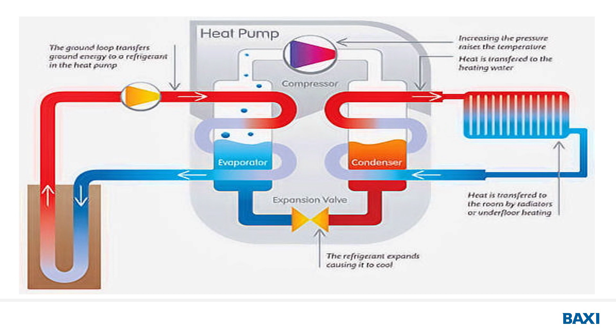The job of the CHP was to be brought into use when the building required extra heat that the ground source heat pump couldn't provide. The CHP would then be diverted to supply the heating and hot water in the building. Bearing in mind, all the time these CHPs are running, they're producing electric. And in downtimes, when the CHPs weren't needed in the building, the ground source heat pumps would be brought in, but the heat from the CHPs would then be dumped into the borehole.